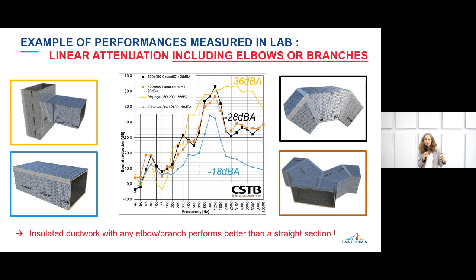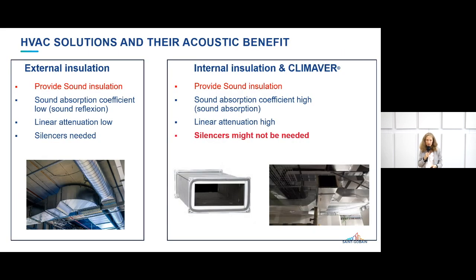And of course, if you decrease the internal section even more, which can happen with the shoe, that's what you have with the yellow line, then you can even increase it by 18 dBA. That is to say that with a linear duct of 2.4 meters plus a shoe of 15 per 20 centimeters, you can reach 36 dBA with this alone, which is quite a lot. So of course, in this case, the more shapes, the better it's going to be, and of course, the smaller the duct, the better it's going to be as well. And I will let Gary give you the conclusions.